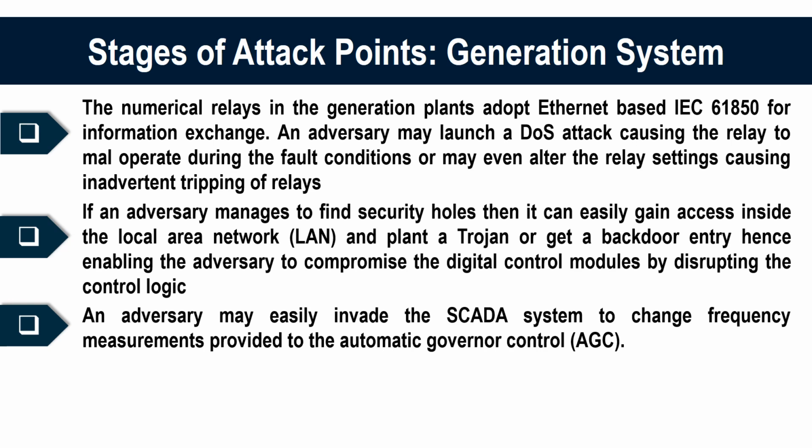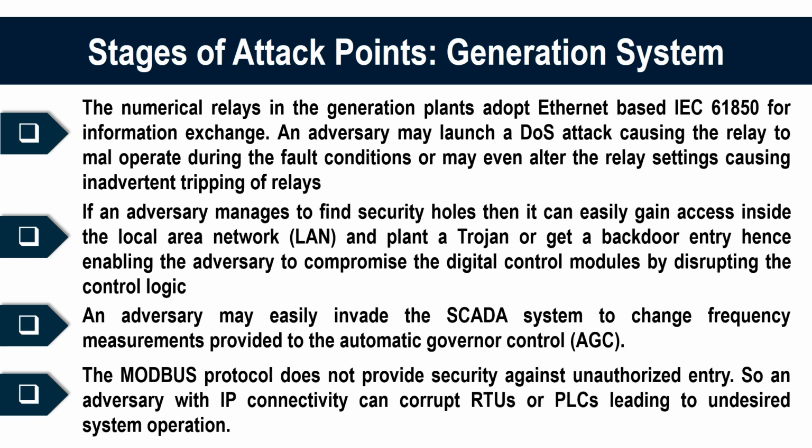And if these changes are coming up in the generation system at the power plant, then the disruption cost for the power disruption will be really high. The Modbus protocol does not provide security against unauthorized entry. If you look at the current Modbus systems, they don't have any encryption or authentication mechanism for transmitting data. So an adversary with IP connectivity can corrupt RTUs or PLCs, leading to undesired system operation.